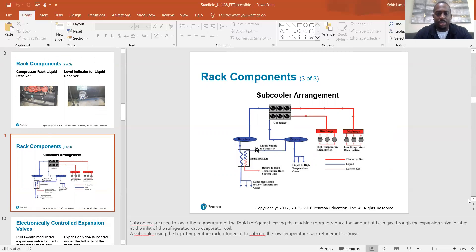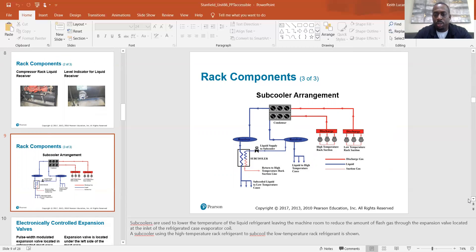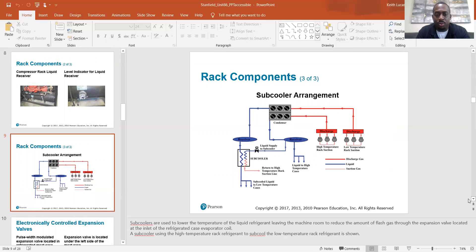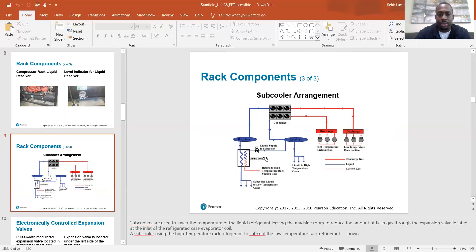Rack components. Subcooler arrangement. So subcoolers are used to lower the temperature of the liquid refrigerant leaving the machine room to reduce the amount of flash gas through the expansion valve located at the inlet of the refrigerated case evaporator coil. A subcooler using the high temperature rack refrigerant to subcool the low temperature rack refrigerant is shown. And so here's your subcooler right over here.